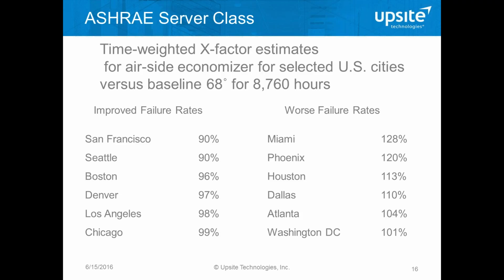And we may decide that's an acceptable risk if we can avoid the expense of building, deploying, and actually operating the mechanical plant. Furthermore, if our experience has been where we're seeing 75-degree inlet rather than the hypothetical baseline of 68-degree inlet, then when we run this data center without any air conditioning, that's only a 7% increase in failure rate. So it's going to take us 4 or 5 years to actually see the one failure, which may extend beyond the cycle of our technology refreshes. So we may never actually see that failure. So this analysis needs to go into the procurement decisions on servers.